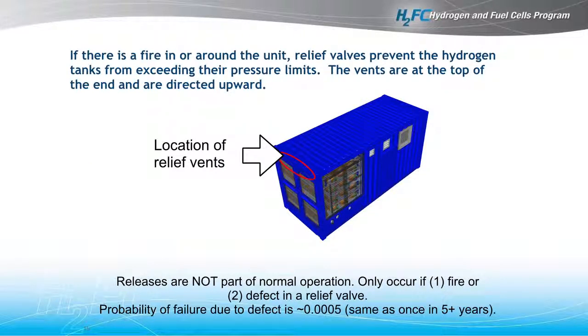If there were fire, then the tanks need to vent because it's pressurized gas, and as the tanks heat up, the pressure rises, so we need to vent that. And there are vents located here that will vent the contents of the hydrogen storage, which is in this area here. And they're in a location that facilitates venting up and away. And we'll talk about the properties of hydrogen, but suffice it to say it's much lighter than air and it wants to rise and dissipate anyway, so this helps to facilitate that. And that's really why there needs to be a release. The only other thing that is a remote possibility is if there's a failure of the safety valves, and that is actually a very, very small chance. And this number of once in 5+ years comes from a very large database that has encompassed many years of data acquisition from many different types of use and different sorts of valves and so forth. It's a national database, and if you really want access to it, I'm sure I can get you to it. But that's a very small likelihood.